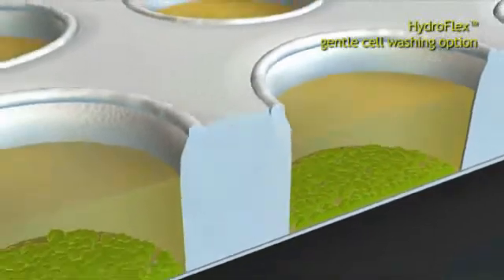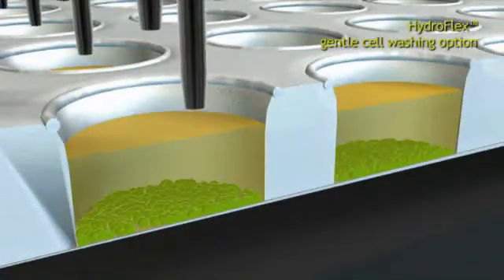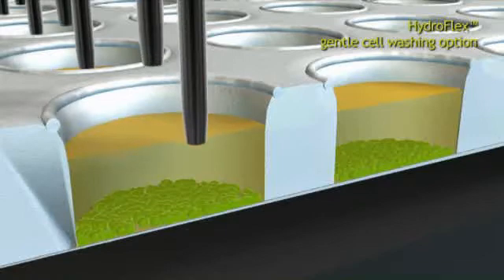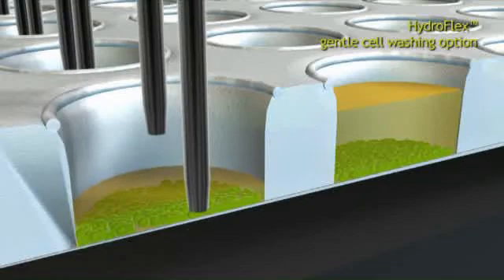Gentle cell washing is implemented by a gentle wash step. While aspirating, the wash head moves down millimeter by millimeter. While dispensing, the wash head moves up with the rising liquid level.